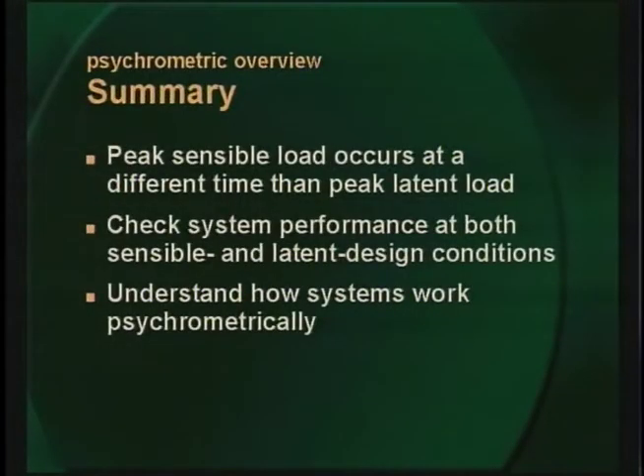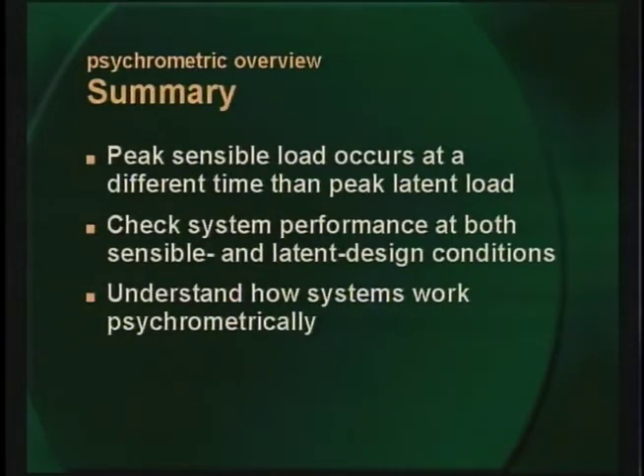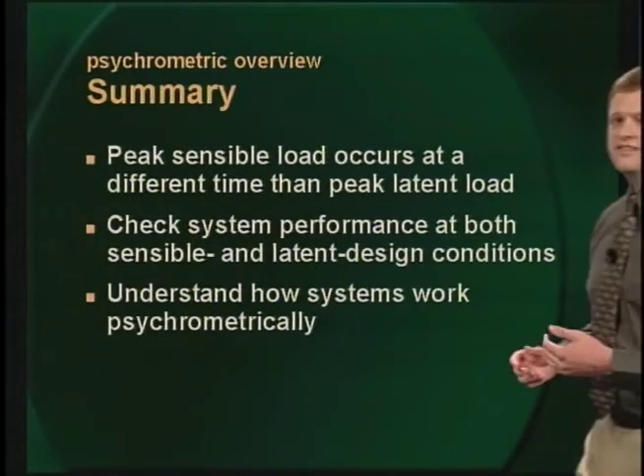In summary, since a peak sensible load rarely occurs at the same time as peak latent load, cooling equipment that is selected to deliver full capacity at one peak is likely to deliver less than required capacity at the other peak. Remember: if space humidity control may be a concern, check the performance of this system at both sensible and latent design conditions. It's important to understand how various systems work psychrometrically at both of these conditions. Next, Dennis is going to review several variations of this basic constant volume system to see how space humidity control performance can be improved.